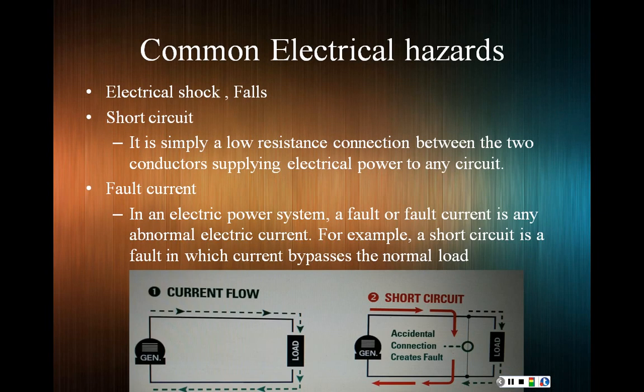Common electrical hazards: electrical shock, falls, short circuits, fault currents. Let's talk about short circuits because they are very important in electrical distribution. A short circuit is simply a low resistance connection between the two conductors supplying electrical power to a circuit. You can see in the picture there is a current flow like a cycle. If the current finds another conductive way, it uses it to make another cycle. You can see the red cycle, the red current. So it is considered a short circuit. I will explain later why it is important.